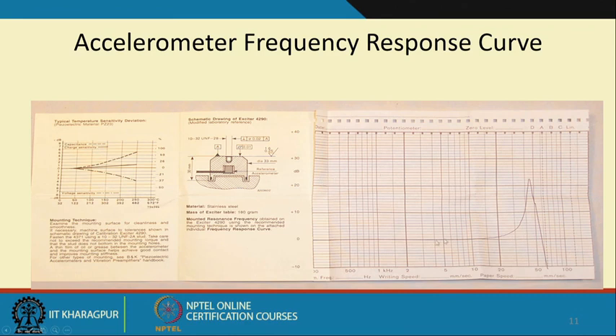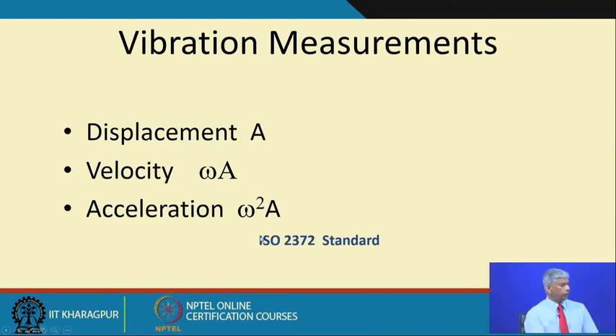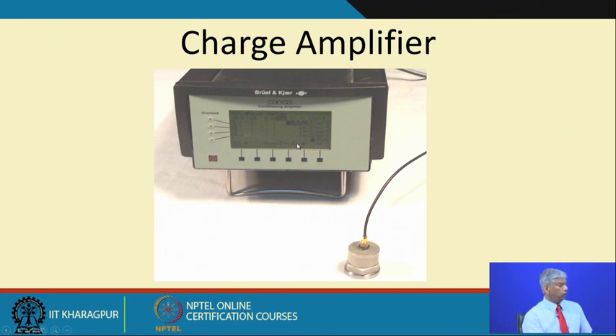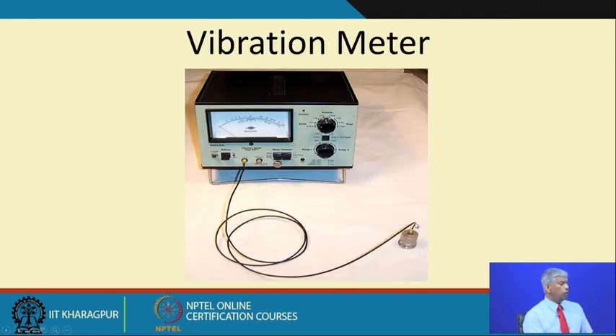When you go to the market to buy accelerometers, you will see charts showing the frequency response and the effect of different mounting methods. There is also an ISO 2372 standard for vibration monitoring which will be discussed in the next class. This is the view of the charge-type amplifier setup: the accelerometer connected via a low-noise triboelectric cable to a charge amplifier with a charge-to-voltage converter and voltage amplifier, and then to a vibration meter.